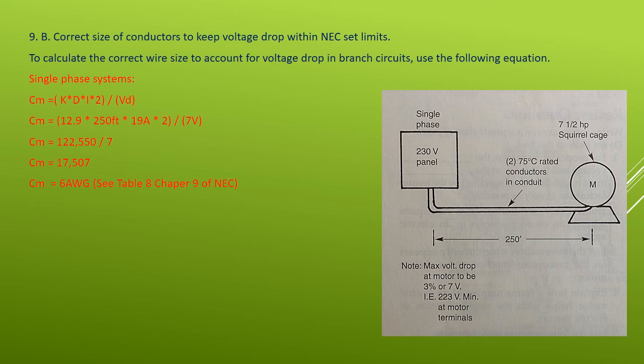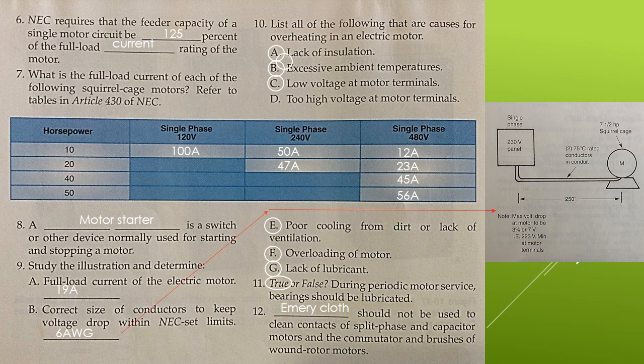Question 10, list all of the following that are causes for overheating of an electric motor. All of these are causes except for D, which is arguably another cause, but it was not discussed in the text, so it was not selected. A, B, C, E, F, and G. Question 11, true or false, during periodic motor service, bearings should be lubricated. Of course, true. And 12, emery cloth should not be used to clean contacts of split phase and capacitor motors and the commutator and brushes of wound rotor motors.